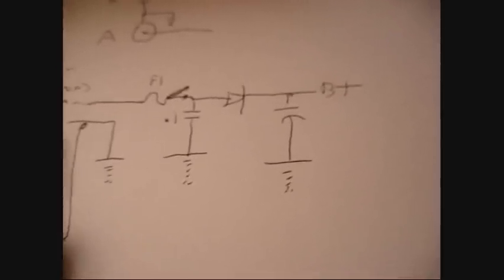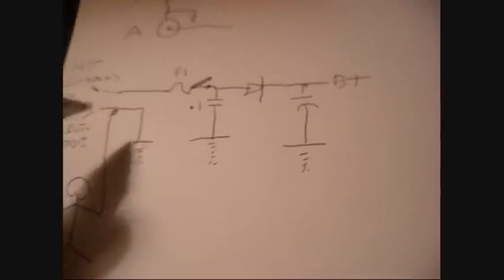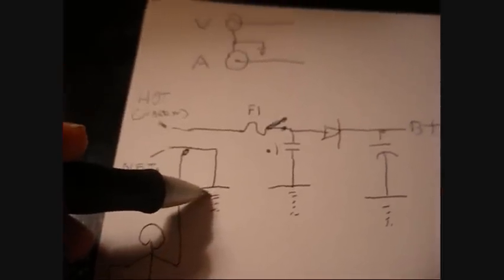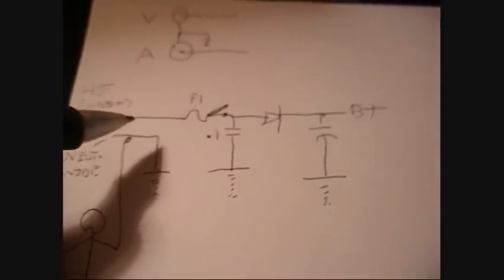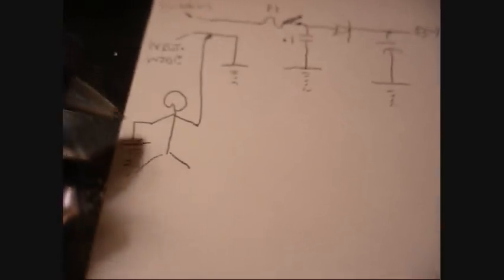But let's say this television was plugged into an outlet wired backwards, or someone filed down the wide prong on the power cord so the plug would fit into a non-polarized older outlet. If that happens, now the hot side of the line goes straight to circuit ground, and the neutral side ends up on the side with our fuse. That's when things get very dangerous. In this situation, if I were to touch something on the set at ground potential, like the outer conductor on these AV input jacks, while touching something with a return path to ground with my other hand, that could very well be the last thing I ever touched.